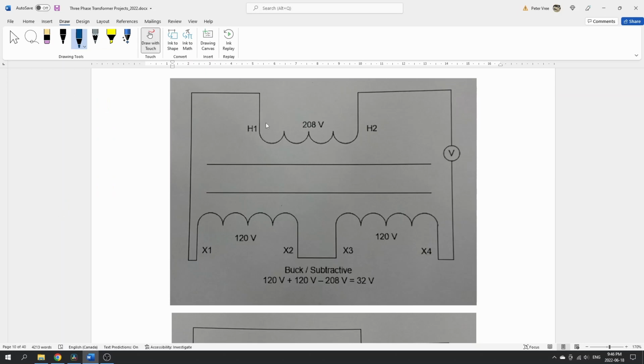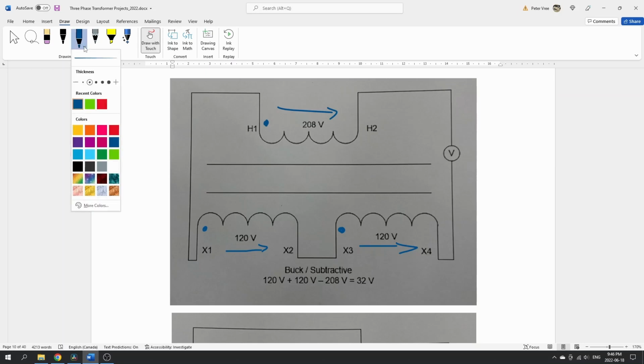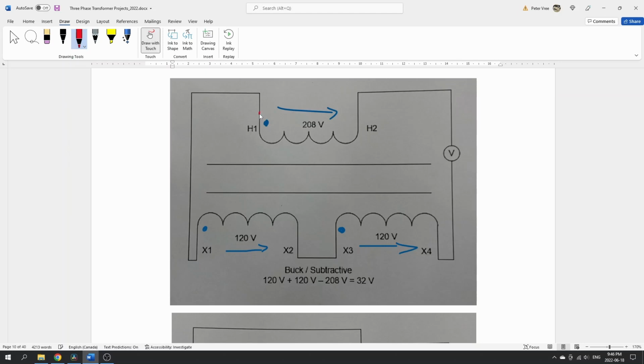For this one, again, I'm going to put the dots here for H1, X1, and X3. We'll put our instantaneous polarity here, denoted with these arrows. This one actually matches what I'm doing in the video, in that I have a jumper here between H1 and X1, and my meter is going to be between H2 and X4.